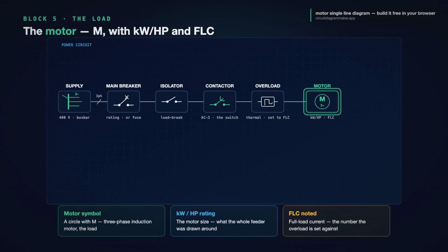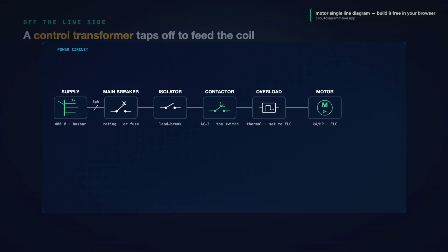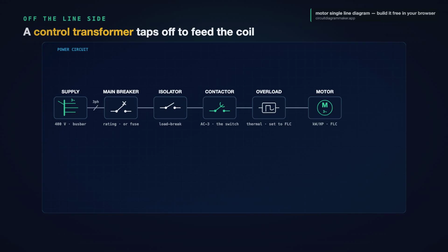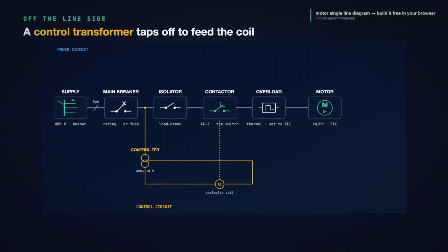Now, one branch we have not drawn yet, the control transformer. Everything so far has been the power circuit, the heavy line that actually switches the motor. But the contactor's coil needs power too, and you do not want that coil sitting at the full line voltage. So a small control transformer taps off the line side and steps the voltage down, often to 110 or 24 volts, to feed the coil safely.